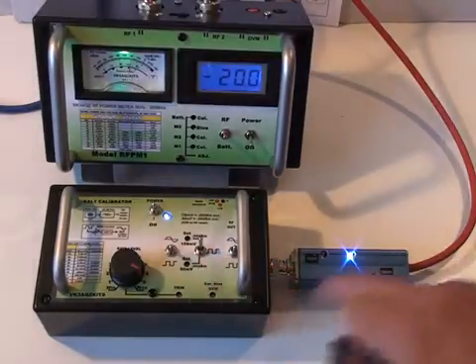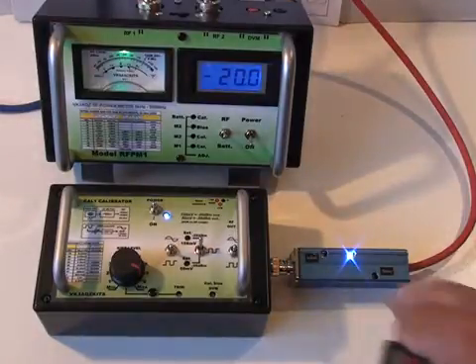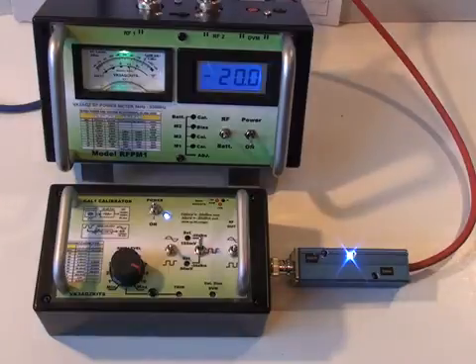So if you wish to measure, for example, the linearity of your detector head over a much wider input range, you really need a very clean sine wave signal.